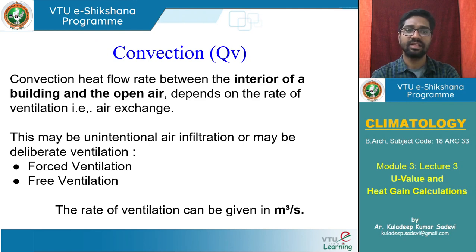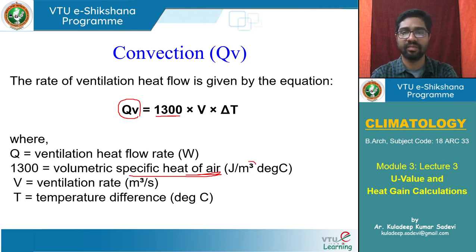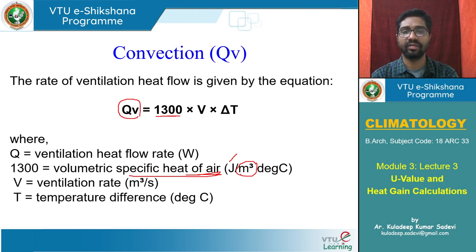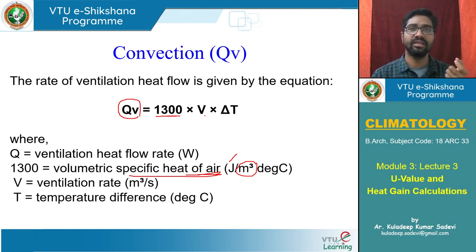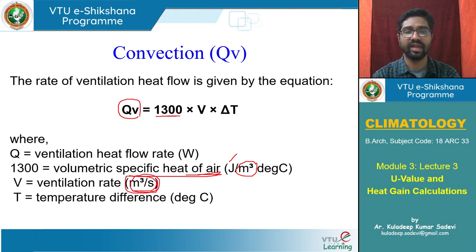For convection heat gain or heat loss, the total heat flow through ventilation is 1300 (volumetric specific heat of air) multiplied by volume of air moving multiplied by temperature change from outside to inside. The 1300 J/m³·°C is the amount of heat required to change the temperature of 1 cubic meter of air by 1 degree. If we know the ventilation rate (volume per second) and the temperature difference, we can calculate the heat added by convection.